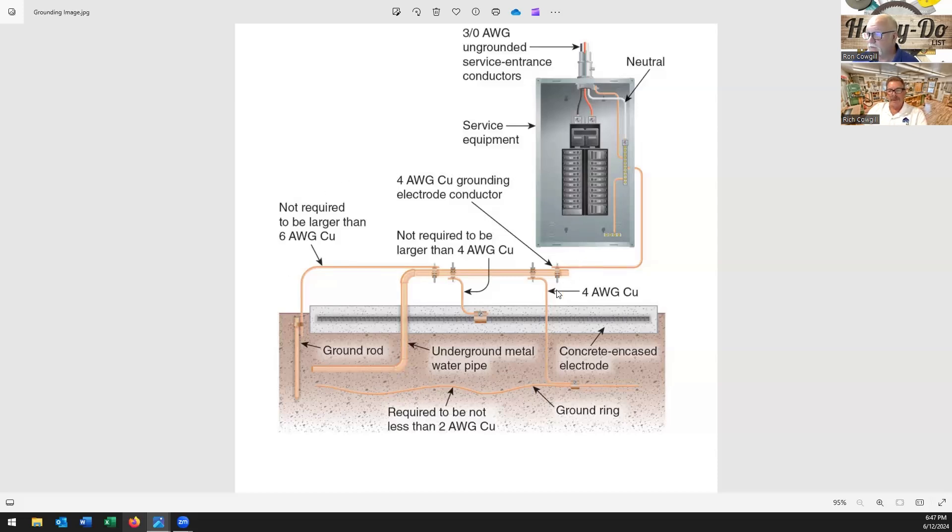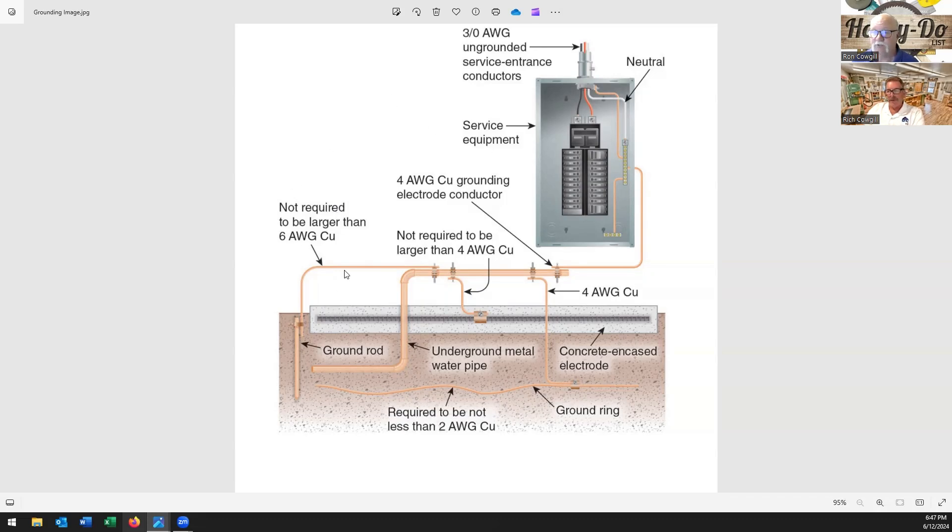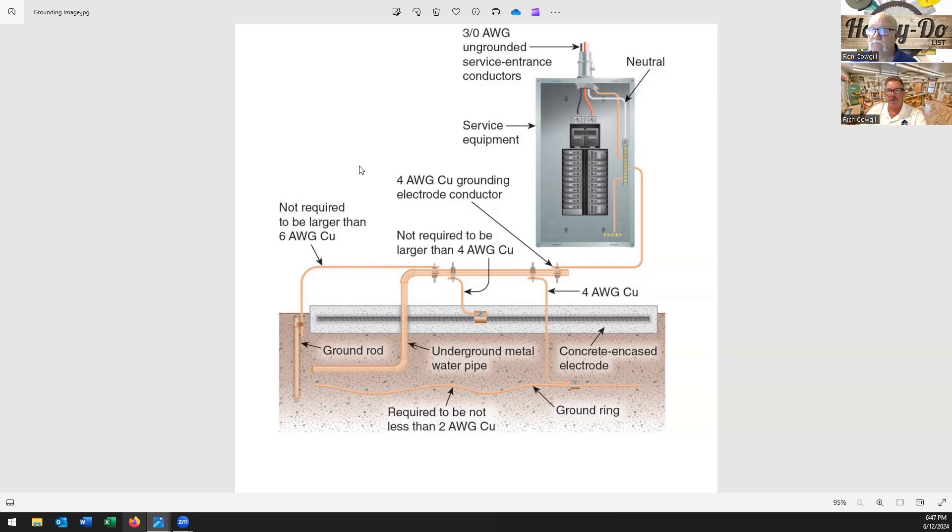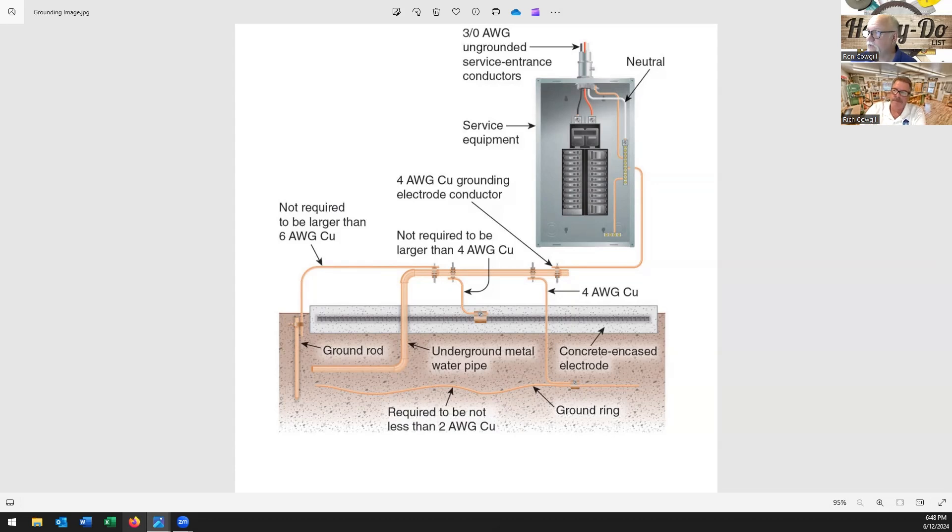So with that, this was pretty interesting the way you have to tie this in with your building steel. In your area you're saying that this actually goes up and then ties in to the building steel. Yeah, it would actually come up next to where your electrical panel is or your service entrance. Blow a hole in the block and if you got a really good guy, which mine was, he put up a two gang plaster ring so that there's a cover on there. But now anybody needs to attach building steel for ground and or bonding, which we'll get to next, then that way they have some place that is - it's guaranteed to work, it's guaranteed it's all tied together. And like you said, that's a low impedance path for static charges, surges caused by environment - anything is getting it back to ground, to the earth. All right, so that is grounding.